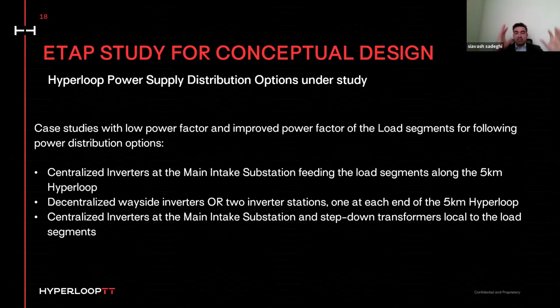So the problem is we don't know if we need to put one set of inverter in the beginning of the track and use that inverter to energize the entire track with multiple switch boxes, which we put along the track, let's say every 250 meter, and we have penetrations and we just feed the linear motors, or we put 2 inverters, one in the beginning, one at the end, and energizing the linear motors, or we do DC distribution along the 5 kilometer and we put one small cell of the inverters at each penetration every 250 meters. So this is a trade-off study that right now ETAP is helping us with, to find the best spot and best configuration from the efficiency standpoint, cost standpoint, and manufacturing standpoint.